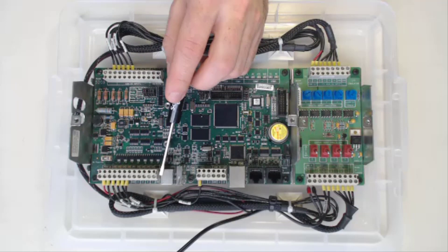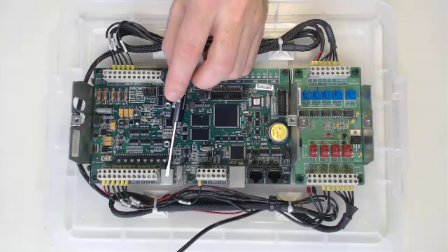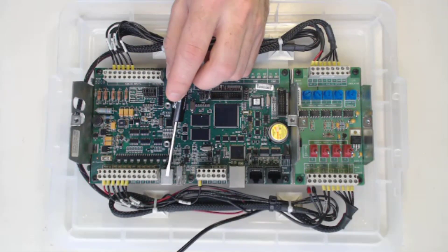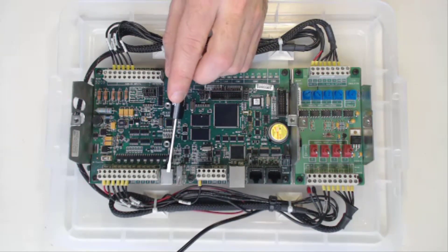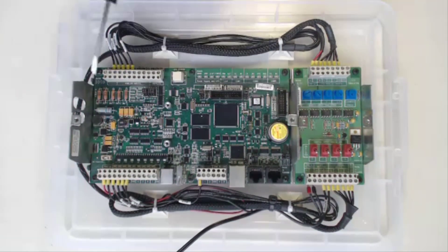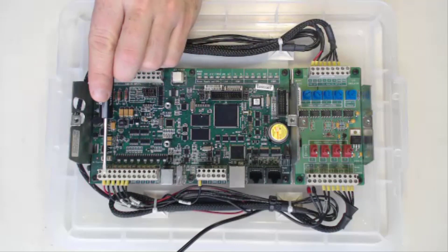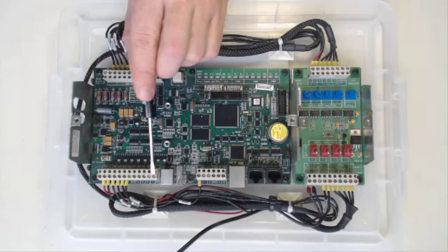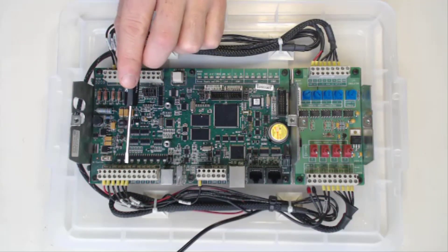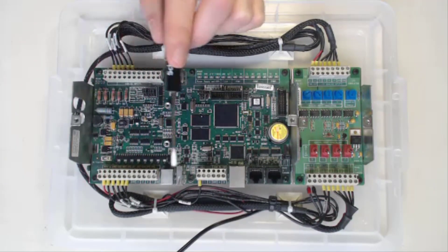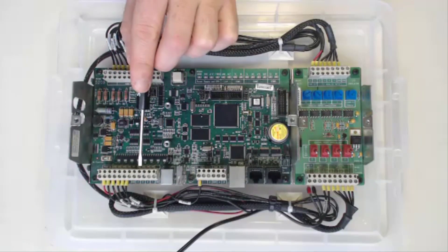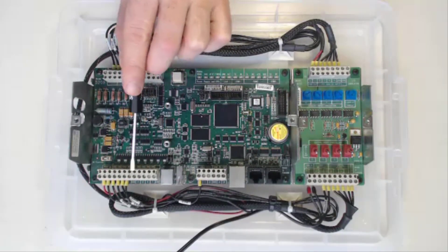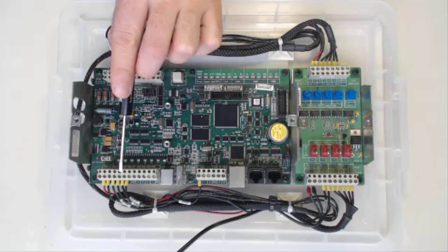The USB B port is where you just plug in from your laptop to the SCADAPack. It does use a USB B cable, which is the same cable as a printer, so a lot of people call it printer cable. As well as you have your DIO. Don't get these confused with DIs and DOs from other Skater Packs—they're wired a bit differently. Be careful of that, and in the program make sure you're only using it as a DI or DO respectively.